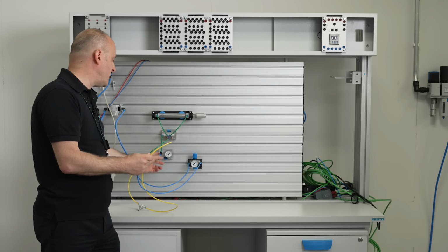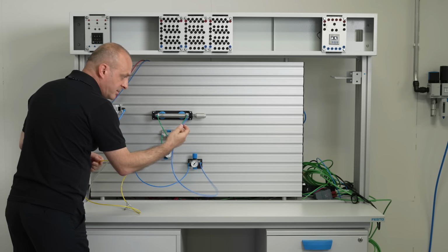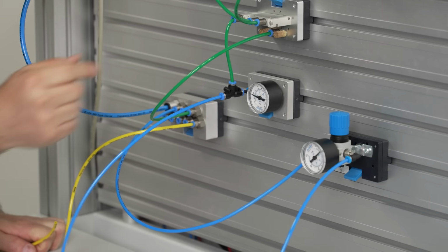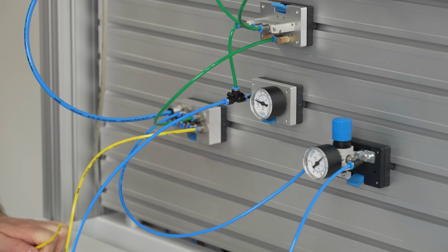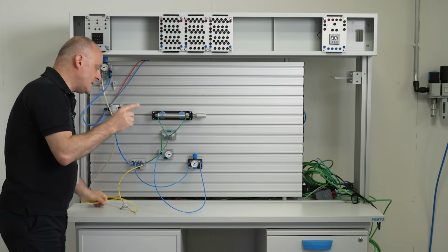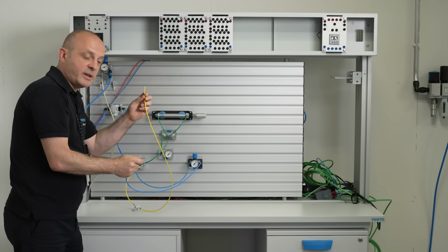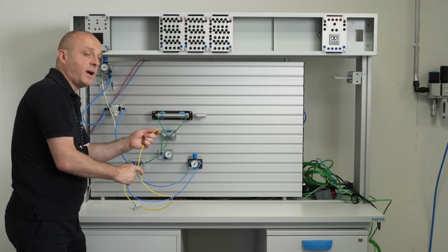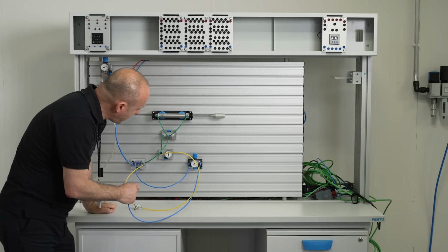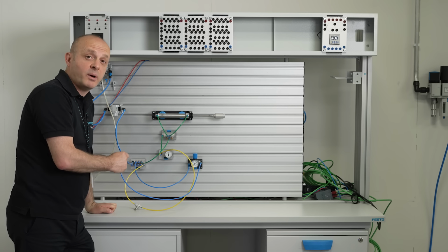To check the pressure, we can use the pressure gauge. What I will do now is install this line, and air is coming out. The valve is not actuated because the pressure we're applying is 1.9 bar. 1.9 bar is not adequate to actuate the valve. This time, I will take this out. No air is coming out because it comes through the flow control valve, and air is restricted. If I put this one back, the pressure is rising and we reach 5 bar. You can't hear it, but we have 5 bar pressure in that.